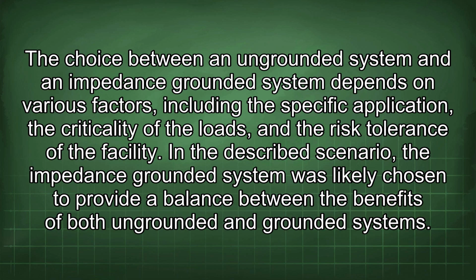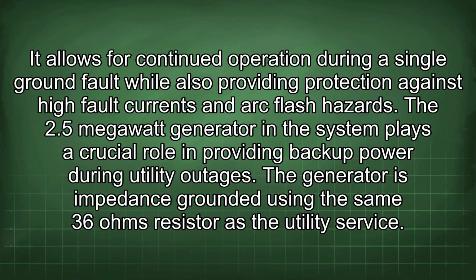The choice between an ungrounded system and an impedance grounded system depends on various factors, including the specific application, the criticality of the loads, and the risk tolerance of the facility. In the described scenario, the impedance grounded system was likely chosen to provide a balance between the benefits of both ungrounded and grounded systems. It allows for continued operation during a single ground fault while also providing protection against high fault currents and arc flash hazards.